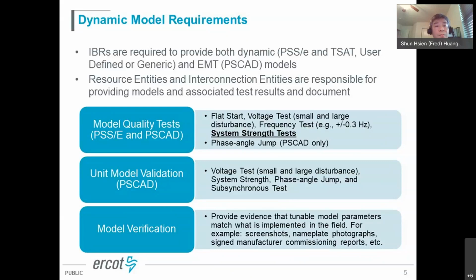All IBRs are required to provide a PSS/E and a PSCAD model to ERCOT as a must requirement. If an IBR wants to connect to ERCOT, they need to provide a PSS/E or TSAT model, and are also required to provide an EMT model, which in ERCOT's case is PSCAD. The resource entity, essentially the owner or developer, is responsible for providing the models.